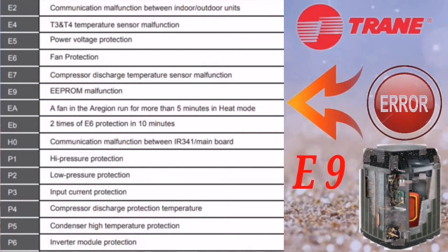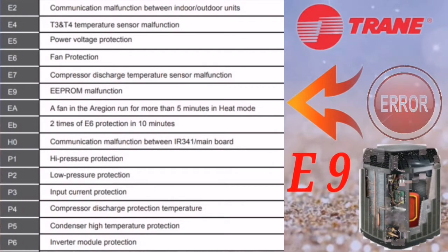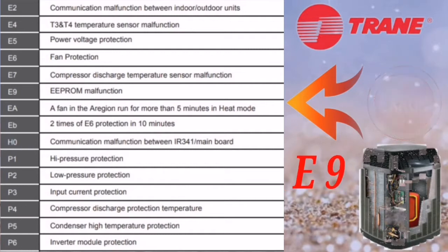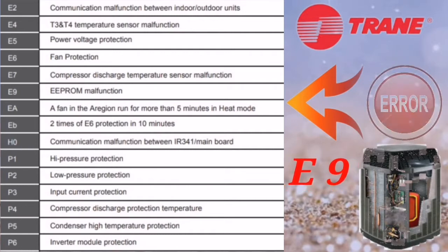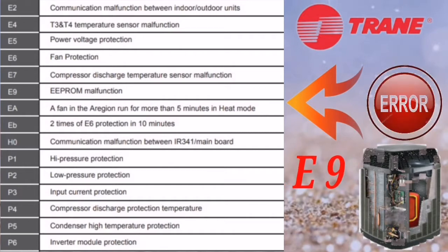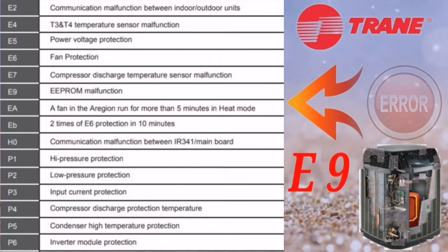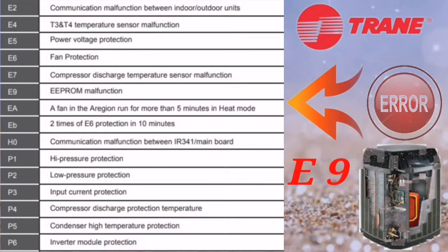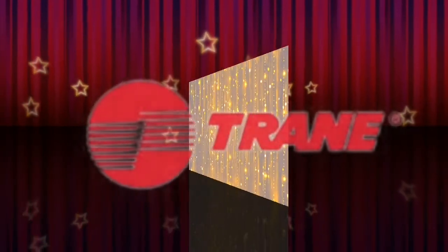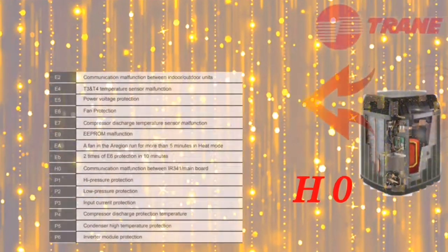The next error code is E9, which means EEPROM malfunctioning. In the outdoor unit, the EEPROM stores all the data from the factory. Without wasting time checking other components, directly change the outdoor PCB and your unit will be in working condition.